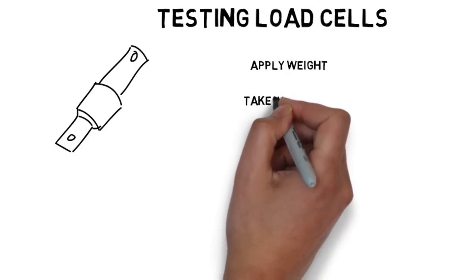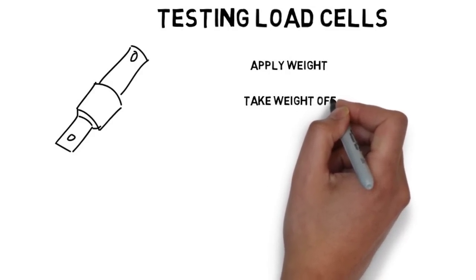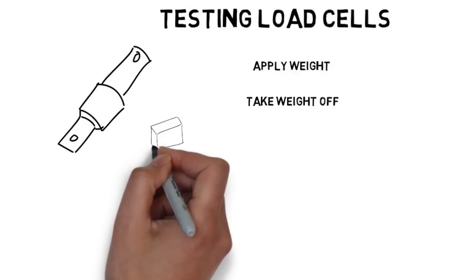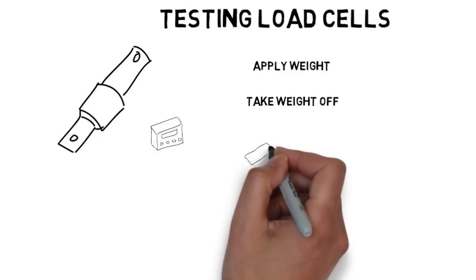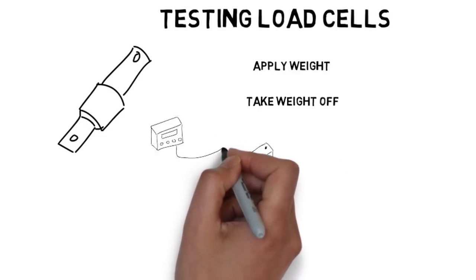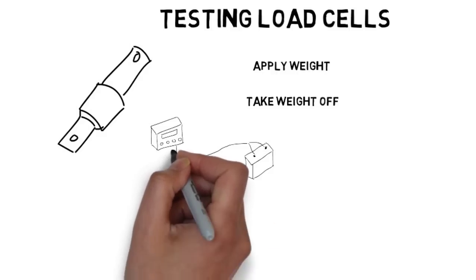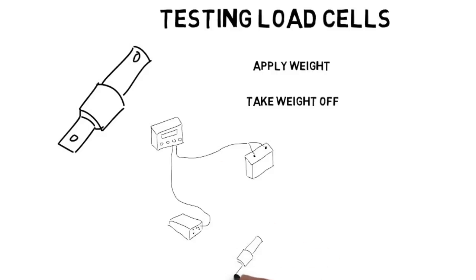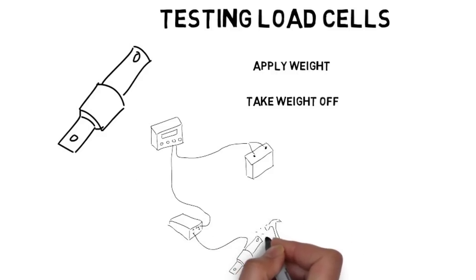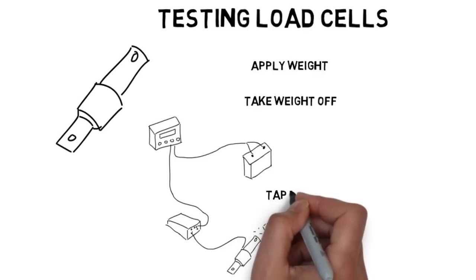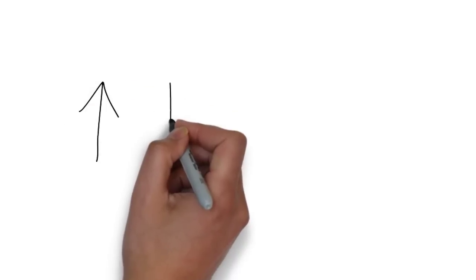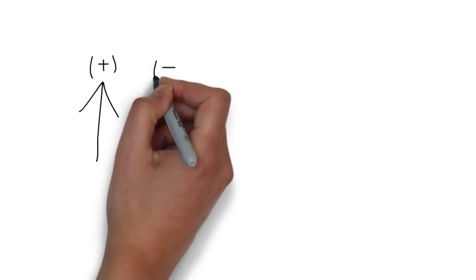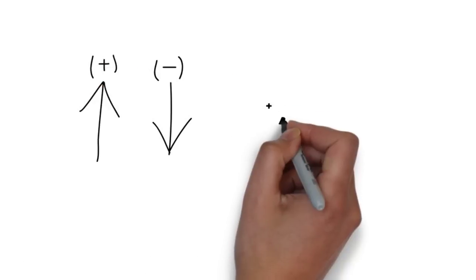The final check to testing a load cell is what I call the tap test. Get your hammer out and tap around the framing where the load cell is installed. As a warning, don't tap on the shroud where the wire enters the load cell. This is a sensitive area. This can cause damage to the load cell. If your load cell drifts or reads erratic while you're tapping on it, the load cell is bad and needs to be replaced.